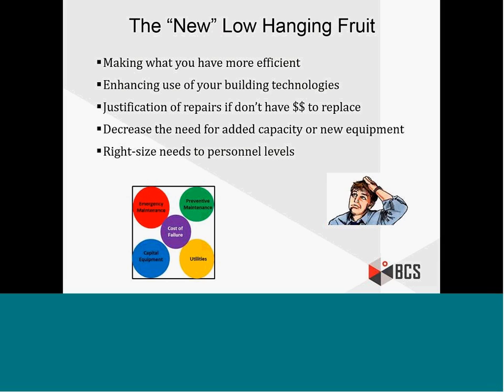Taking those efficiencies and using them for possibly justifying repairs if you don't have the dollars to replace equipment. If you have the right data—in the past you'd do that calculation on lighting replacement or drives, comparing the wattage before and after. But now if you can track information, make a repair, and go back, you can actually prove what those savings were. If you do it on a couple pieces of equipment, you can use that as justification to get more funding for further upgrades and repairs across your portfolio.